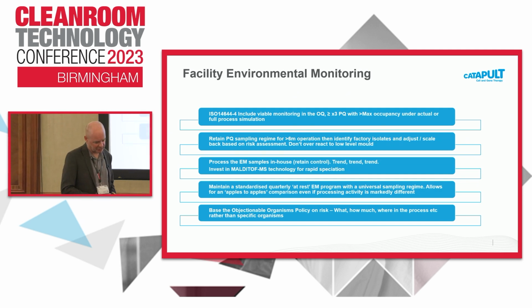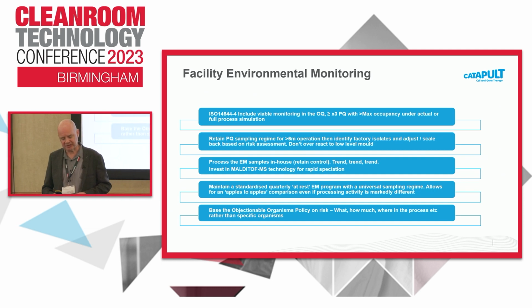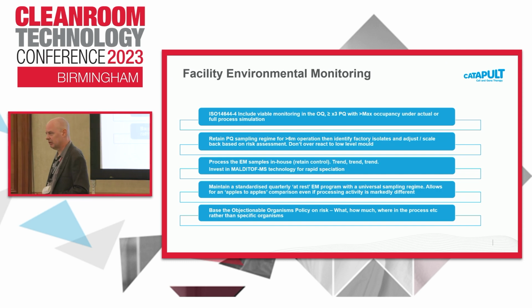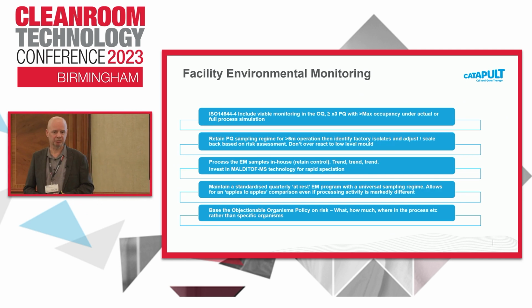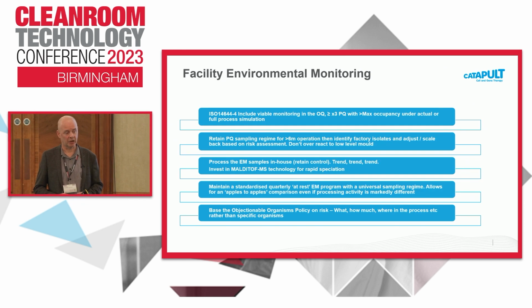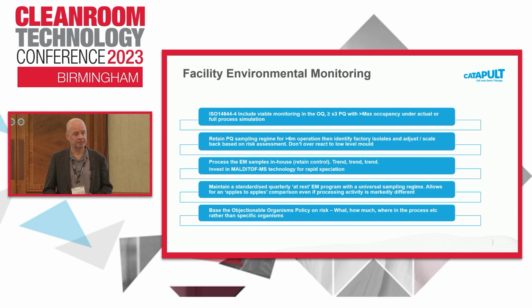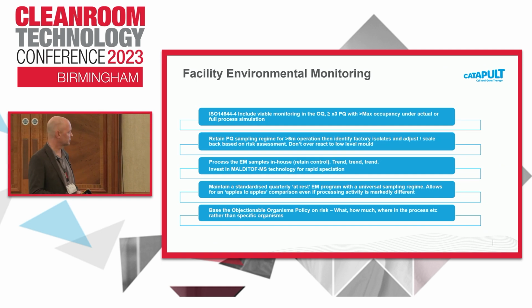And another point to make, through bitter experience, people tend to be extremely sensitive to the evidence of low-level mold in their grade C clean room spaces. Now, mold is ubiquitous, it's everywhere. You're not going to completely avoid it, and as long as the levels are within your action and alert limits, and as long as the mold species doesn't suggest that you've got a potential reservoir within your facility, then it's really just a result of mold tracking in through personnel and material movements. It's undesirable, could be considered objectionable, given where it might appear in your process or where physically that appears, but it's not the end of the world.